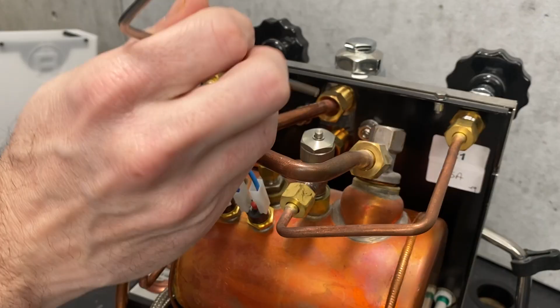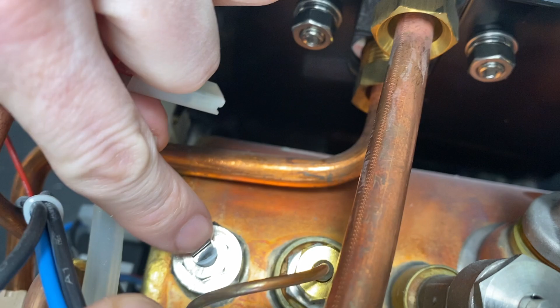We come over to here, we get this red wire coming off. This is your liquid level probe, a piece of metal that goes straight down into the boiler. As we said, how this works with the water sensor for the cup, it's the same idea up here. As the water fills the boiler and comes up, it will hit that piece of metal, probably right around there. So your boiler's at a slight angle, but it's full of water up to wherever it hits that probe.